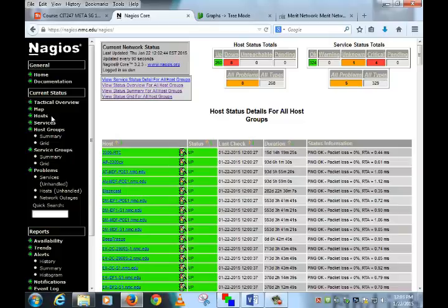And we actually, that happened once. We lost power to the data center and the generator did not kick on like it was supposed to. The batteries in the UPS went dead in about 12, 14 minutes. Happened on a Sunday afternoon. I'm sitting in church, and all of a sudden I start getting notices: switch down, switch down, switch down. It's like, oh, we had a power failure on campus. You can see it just rolling through my pager, boom, boom, boom, and all of a sudden it stopped.